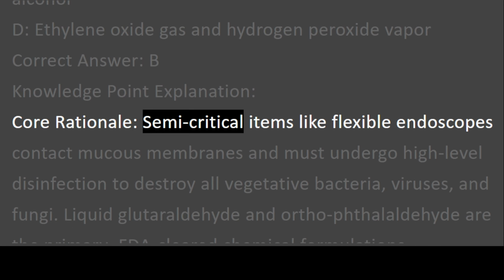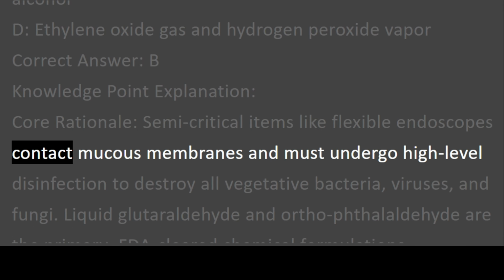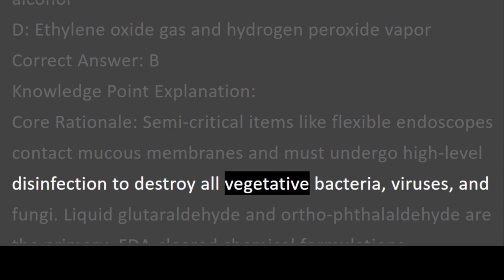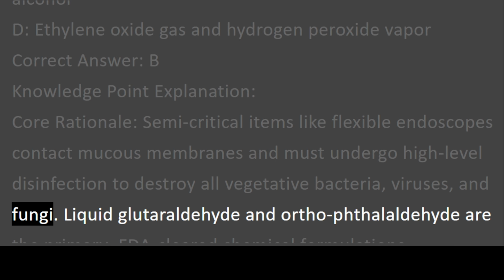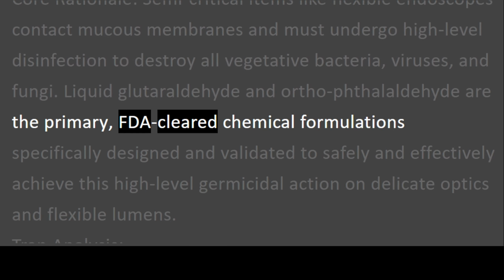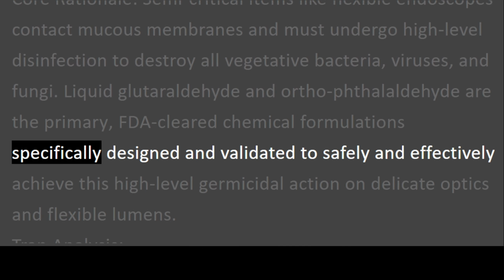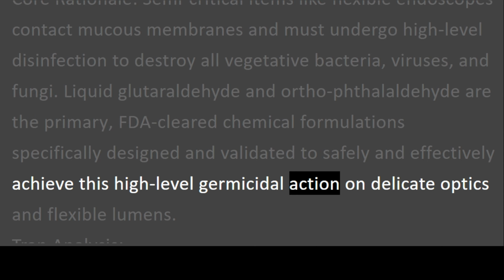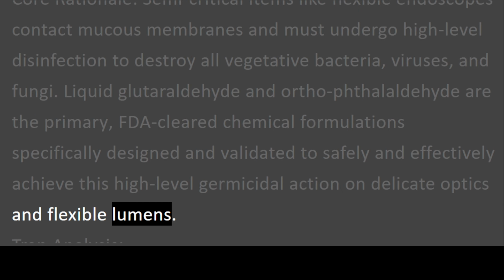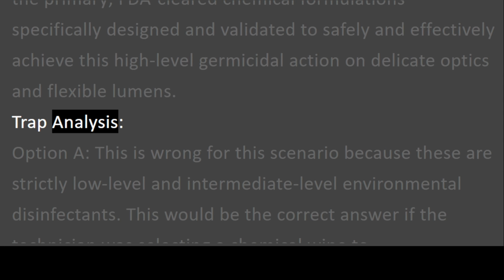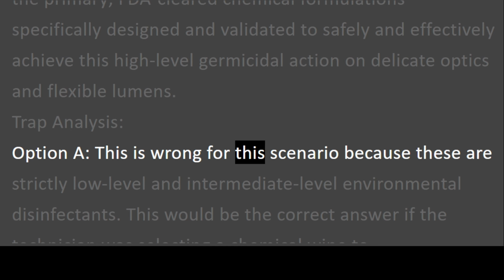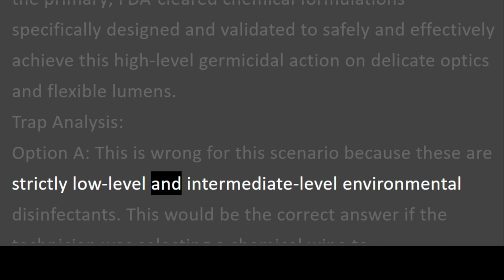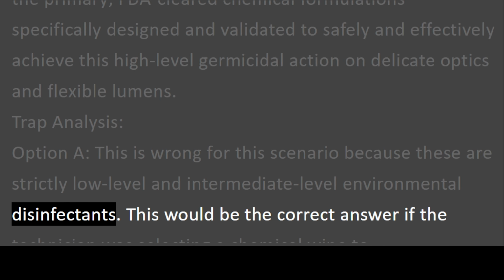Core rationale. Semi-critical items like flexible endoscopes contact mucous membranes and must undergo high-level disinfection to destroy all vegetative bacteria, viruses, and fungi. Liquid glutaraldehyde and orthophthalaldehyde are the primary, FDA-cleared chemical formulations specifically designed and validated to safely and effectively achieve this high-level germicidal action on delicate optics and flexible lumens. Trap analysis. Option A. This is wrong for this scenario because these are strictly low-level and intermediate-level environmental disinfectants.